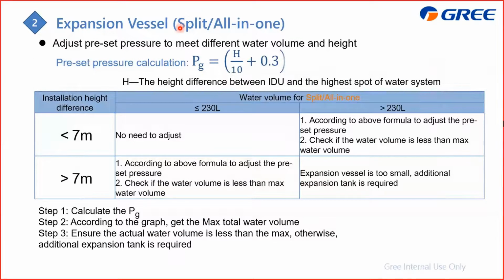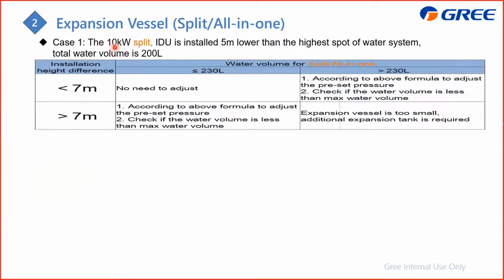And the next is for the split and all-in-one type. For this one, the formula for the PG is the same. The difference is that we also make it into a table, and you just follow the table, and according to your actual installation, you can choose whether you need to adjust it or not. Also, to show you a detailed example, this type is a 10 kilowatt split type. The indoor unit is installed 5 meters lower than the highest point of the water system, and the total water volume is 200 liters. According to this table, it belongs to this part, and it is less than 230 liters, which means no need to adjust.